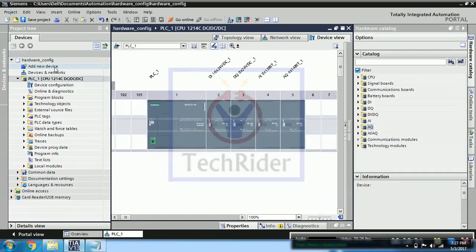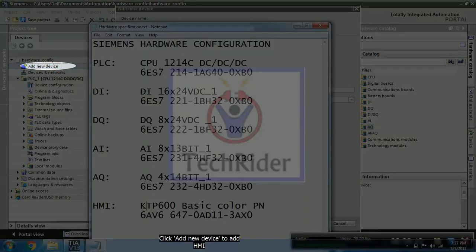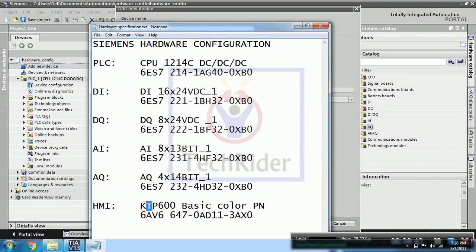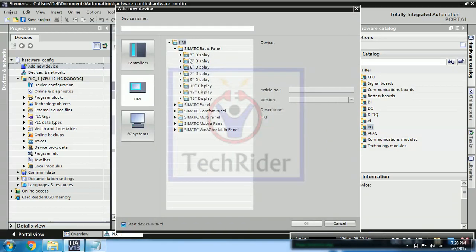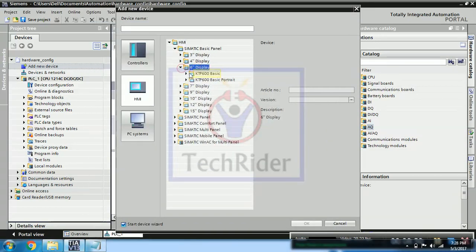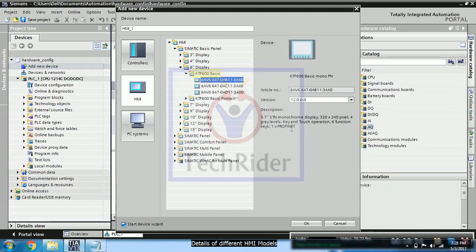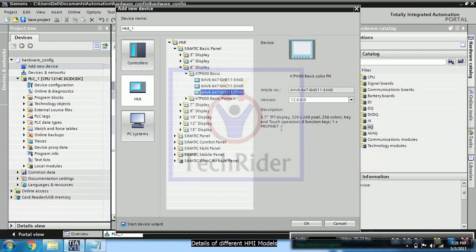Now once this is done we can add our HMI, that is KTP 600. It is Key Touch Panel HMI, 6 inch HMI. So we have to select KTP 600 basic. And you can see few variants having different communication protocols like PROFINET or MPI, PPI. So we will go for PROFINET with color display.